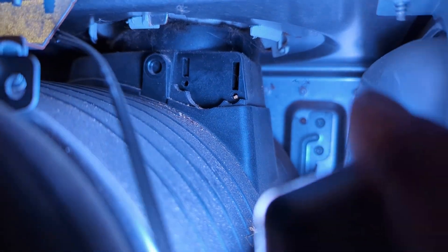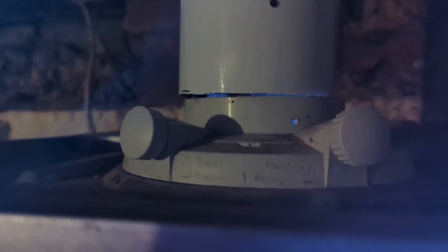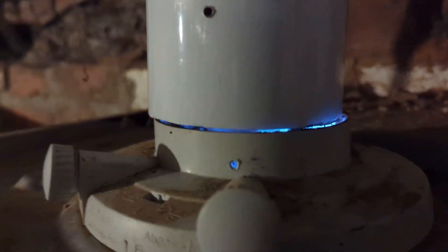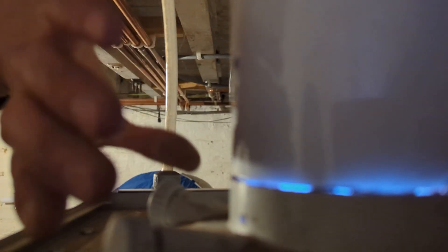Spoke to Vaillant, they informed me it needed twisting, and there's a little catch — as you can see there, that little white catch that needs pushing in. Whilst pushing that in, you need to twist the flue adapter to the right, then it pulls off.